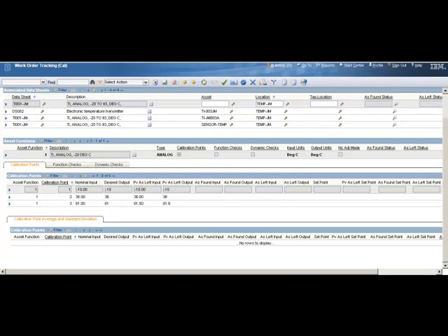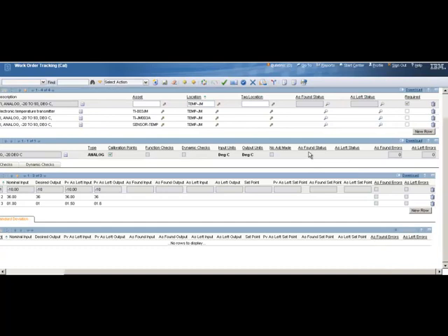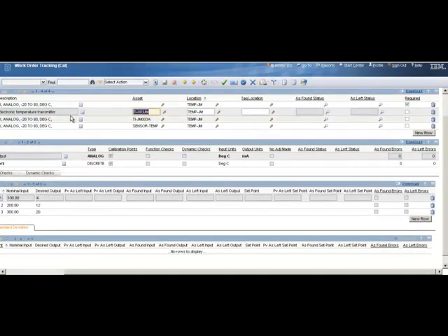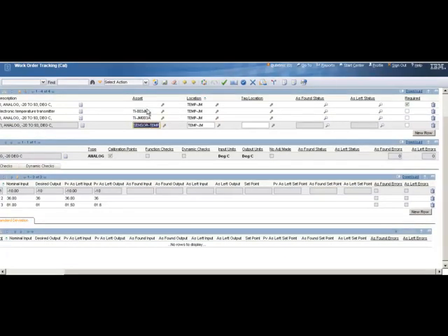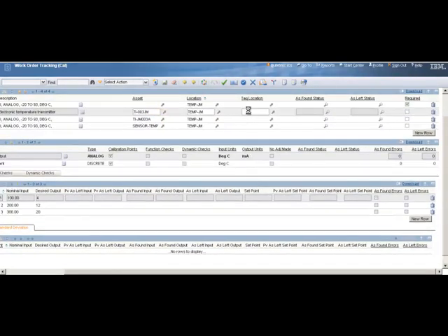Now, we mentioned before that for loop calibrations, and we'll complete this out in a little while, only one data sheet is required, even though I assigned 4 data sheets to that particular location at the job plan level. This top one is my data sheet for my loop by itself. So if I perform a calibration on the loop and it passes, I don't have to perform any of the other ones for the components. Now, if I perform my loop calibration and it fails anywhere, then my other data sheets are here. I can just select them and, while I've got all my equipment out, calibrate the transmitter, the indicator, and the sensor.